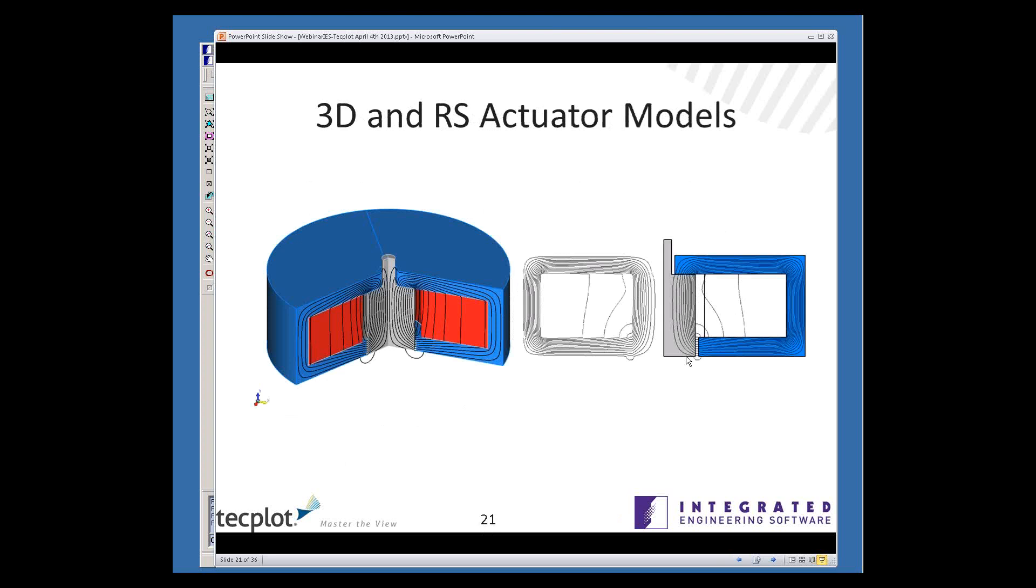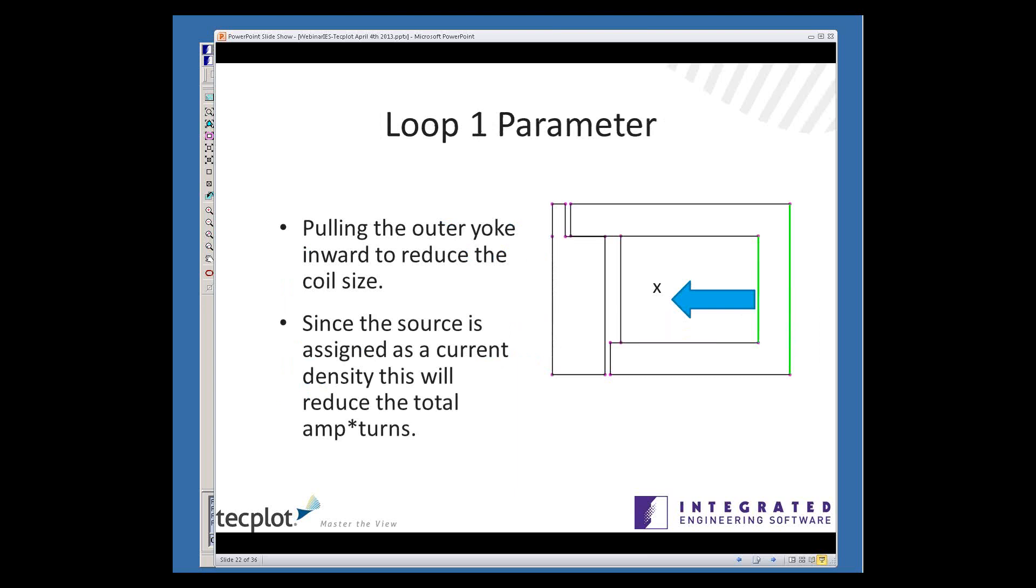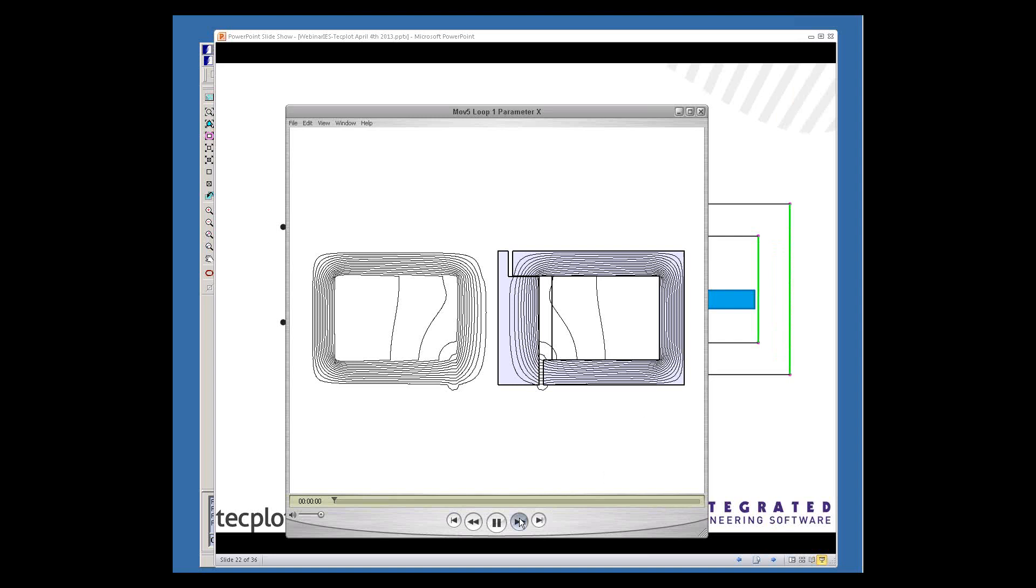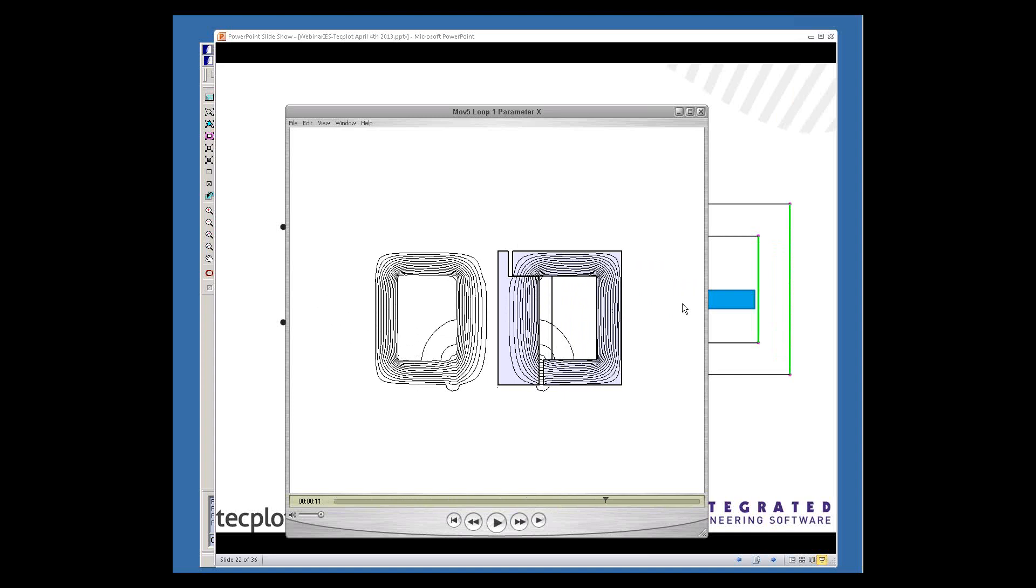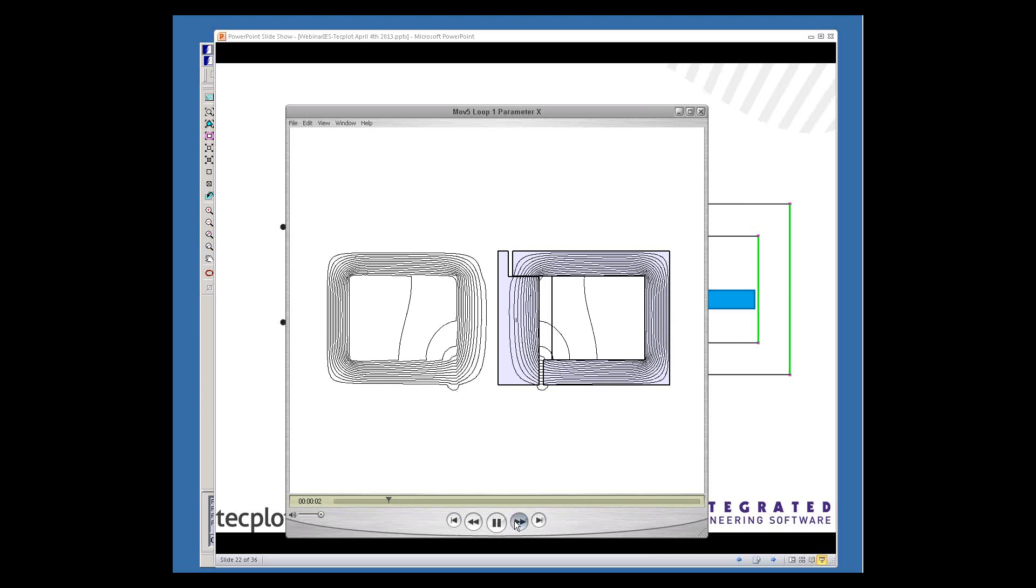Let's go back to that push actuator. Let's consider both a weight constraint and a fringe field limitation. The latter has to do with its proximity to additional electronic equipment. The former has to do with its aerospace usage. Consider this cross-section on the right. We're going to use it in a rotational symmetric embodiment. The easiest way to do that is to look at three ways to reshape this device. Consider the first variable, we'll just call it variable X. We're going to reshape the device by moving the right-hand side of that yoke inward. And that does two things. Not only does it reduce the weight of the yoke, it decreases the total amount of current that's going to be useful for creating hold-down force on that actuator, specifically the armature that's in the center.